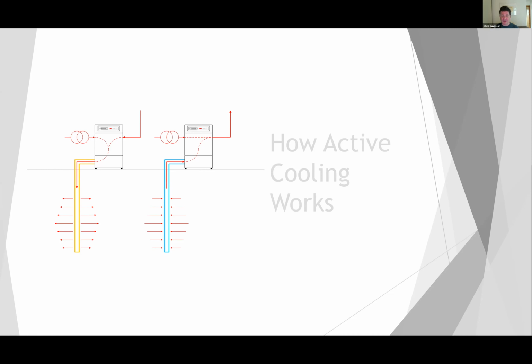It's an important point to realise that you'll very often see very complicated spreadsheets with consultant engineers trying to balance to the nearest kilowatt hour the energy taken from the building or put into the building, but that completely forgets the point that the compressor energy is added to in heating mode and contributes to the load on the ground in cooling mode. So that's how active cooling works.